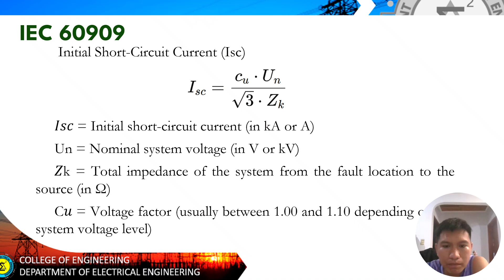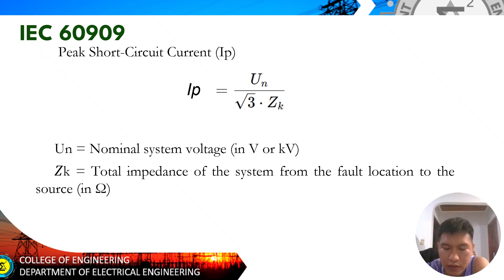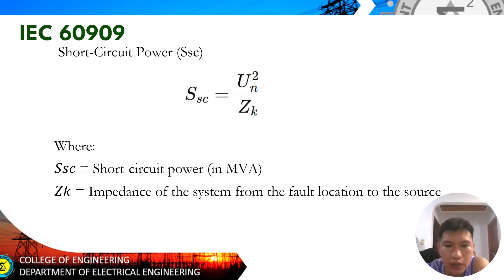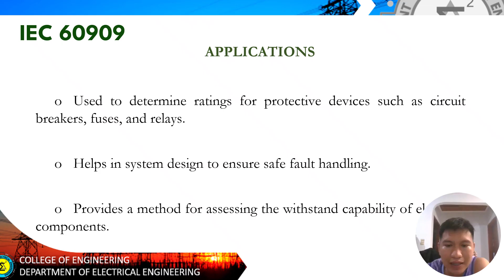Ayan, sa peak short circuit naman, current, okay, yan, yung nominal voltage over square root of 3 times the total impedance of the system from the fault location to the source. Same in ohms. Short circuit power or SSC. Okay. So, ayan, yung ating formula. Short circuit power in MVA. And then yung impedance of the system from fault location to the source. Used to determine ratings for protective devices such as circuit breakers, fuses, and relays. Helps in system design to ensure safe fault handling and provides a method for assessing the withstand capability of electrical components.